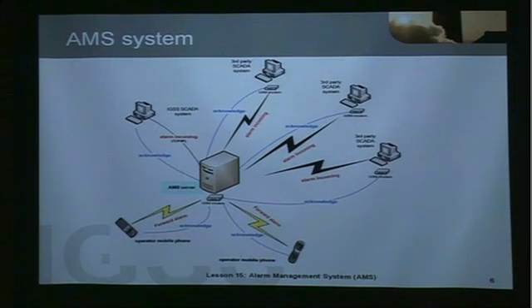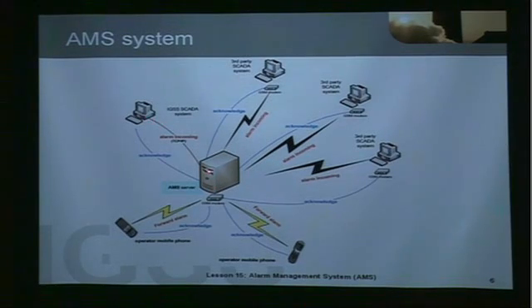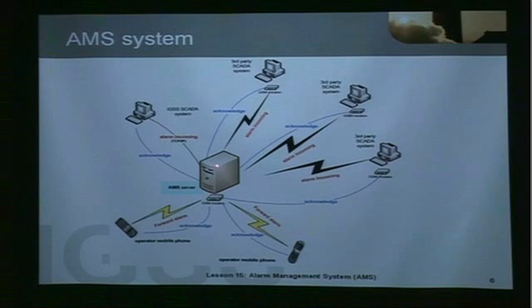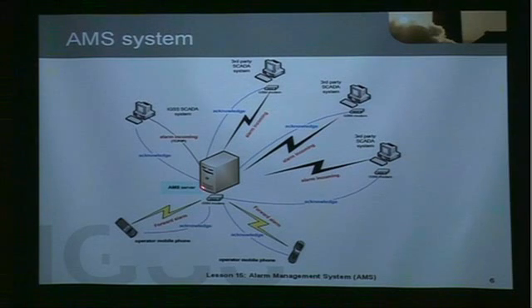Here we have an overview of an AMS system which we could configure with various SCADA systems. In the center here we have the AMS server — the collection point for alarms from all of these various systems. Here we see an IGSS system communicating with the alarm server via a TCP/IP connection. Here we have a couple of other third-party SCADA systems; they communicate with the AMS server via a GSM modem, sending their alarms to the IP address at the AMS server. Alarm acknowledgement can occur out to the various SCADA processes, or alarms can be forwarded to operator personnel on their cell phones, who are then able to acknowledge the alarms back to the AMS server.